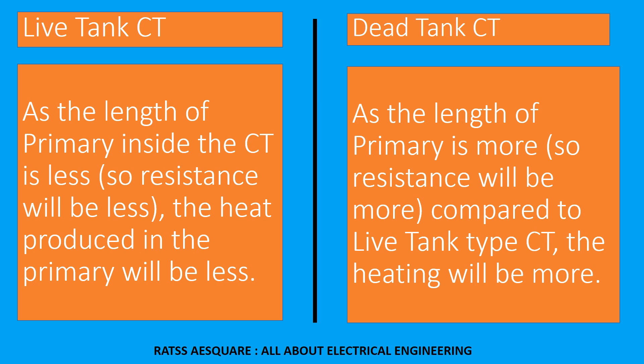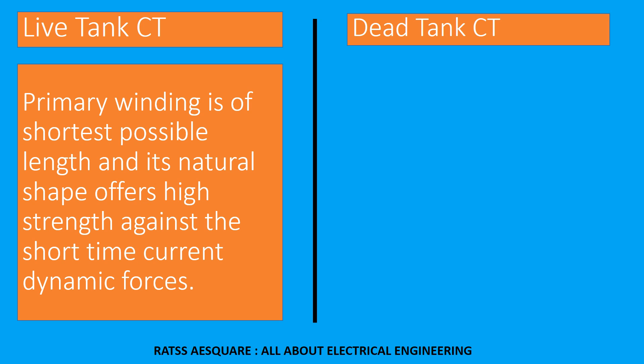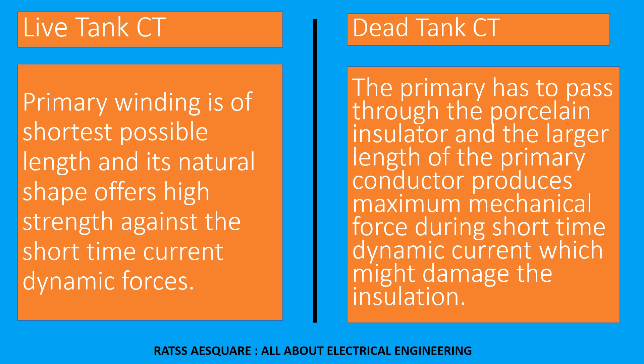In live tank CT, the heating will be less — the primary winding is of the shortest possible length and its natural shape offers high strength against short-time current dynamic forces. In dead tank CT, the primary has to pass through the porcelain insulator, and the larger length of the primary conductor produces maximum mechanical force during short-time dynamic current, which might damage the insulation.